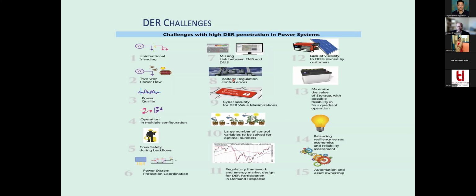With increasing DERs, voltage regulators will not work as they are designed and set. So we need to adjust that and do more frequent control. We wish to do voltage regulation sometimes on a monthly timeline—like you set it, and if there's no DER, you don't need to change it again, because it will operate fine since you know the load profile. But if the load profile is changing, like a duck curve, even at the distribution level, then you need to control voltage regulation settings more often, sometimes throughout the day.